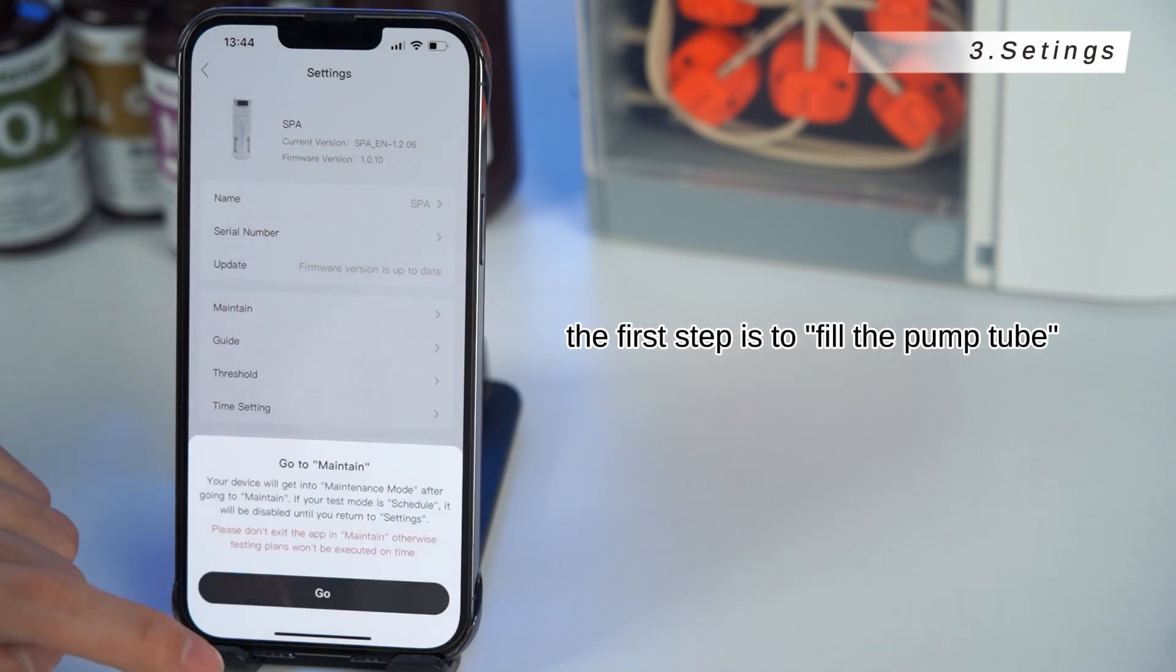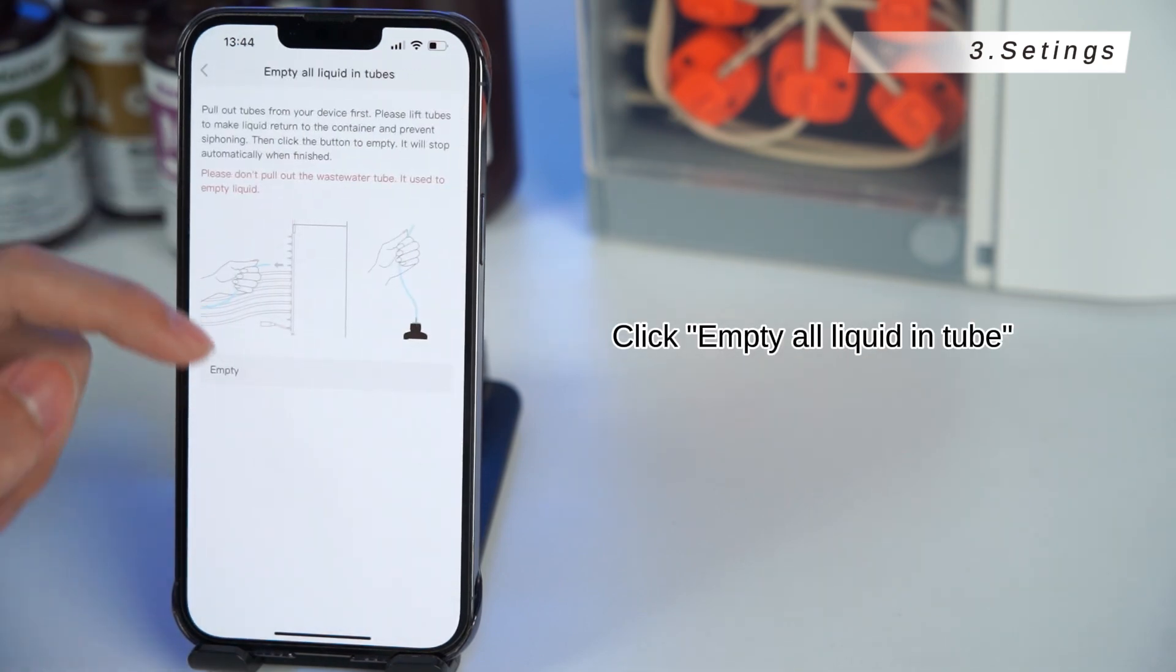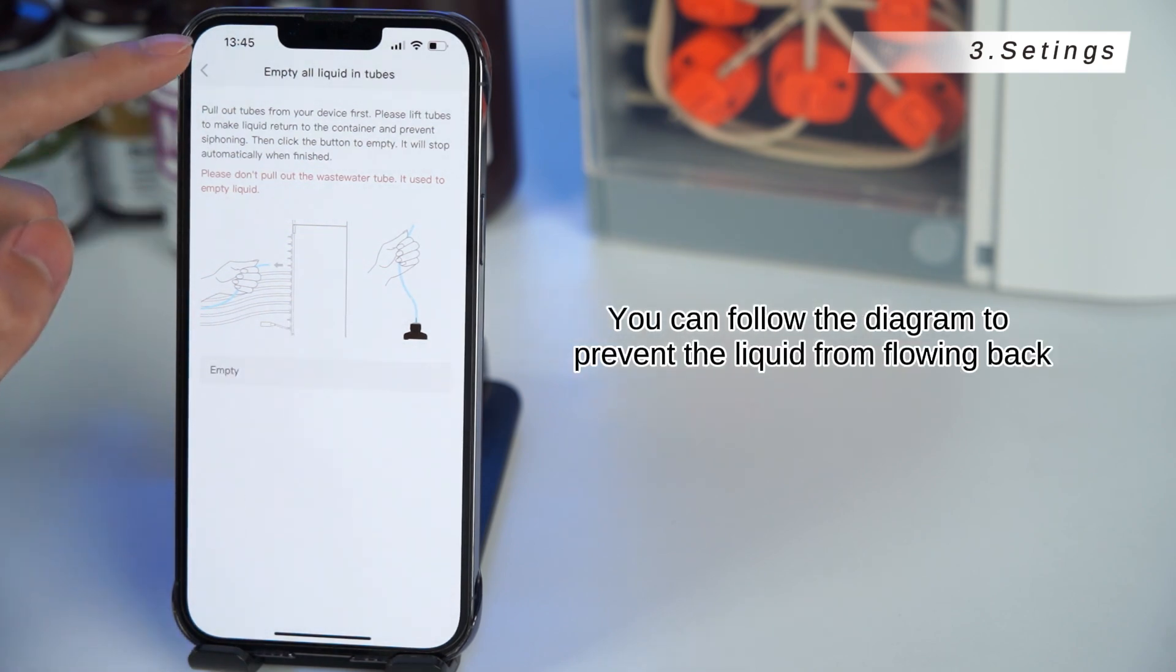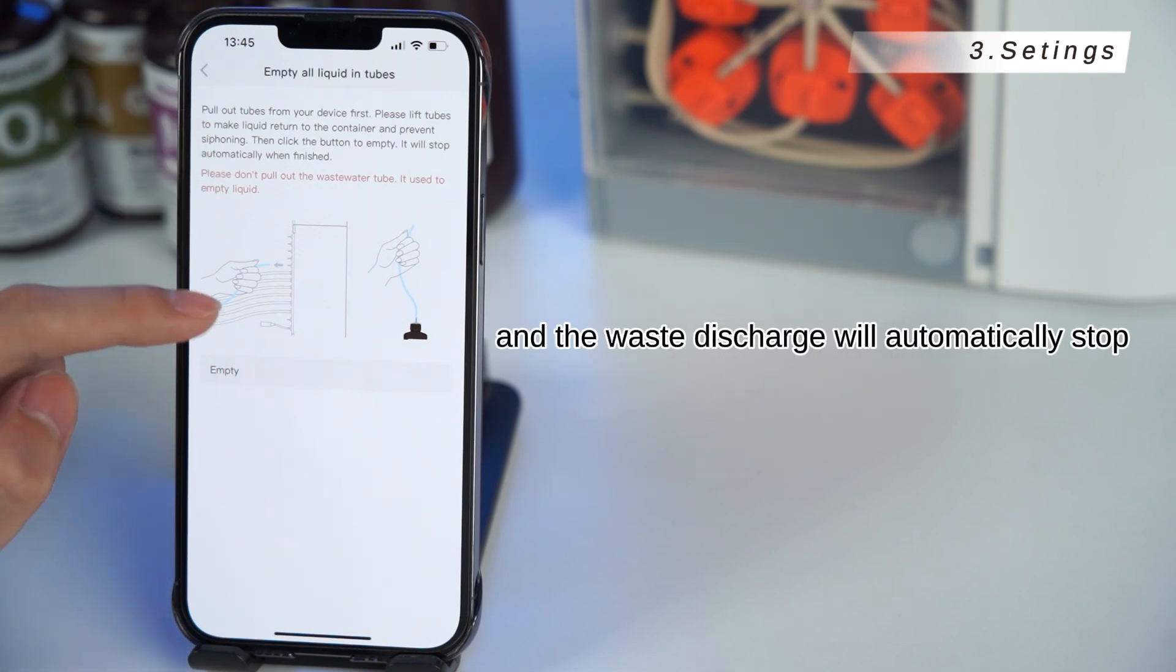Maintain. After entering, the first step is to fill the pump tube, which we need to do when we use it for the first time. Run pump, click empty all liquid in tube. Before emptying, unplug the other pipes of the waste liquid pipe from the machine. You can follow the diagram to prevent the liquid from flowing back. Click empty again, and the waste discharge will automatically stop.